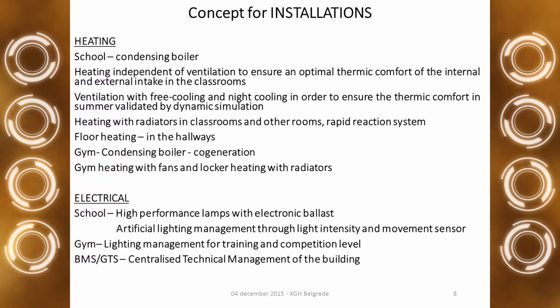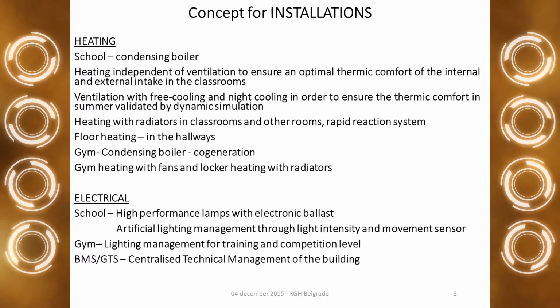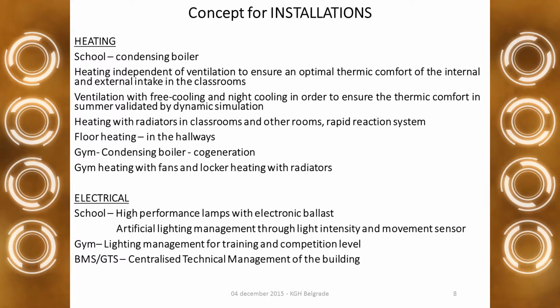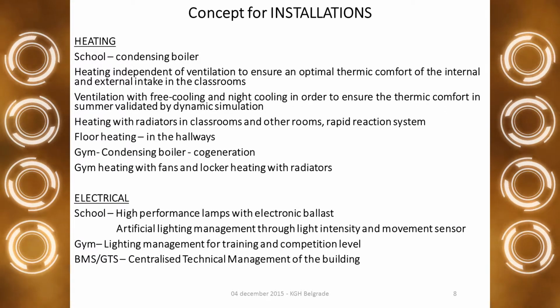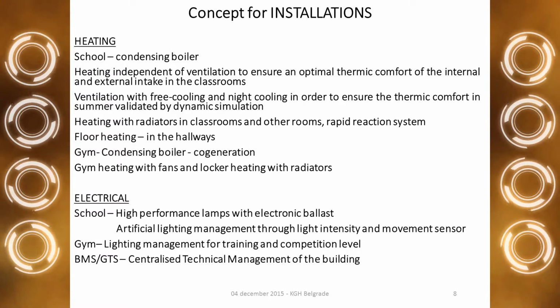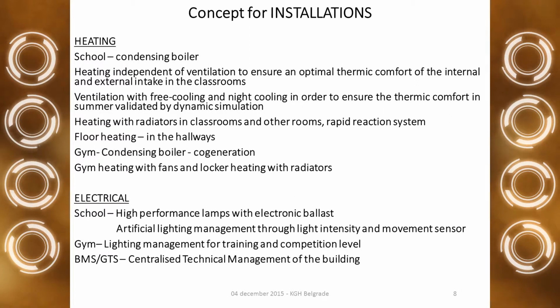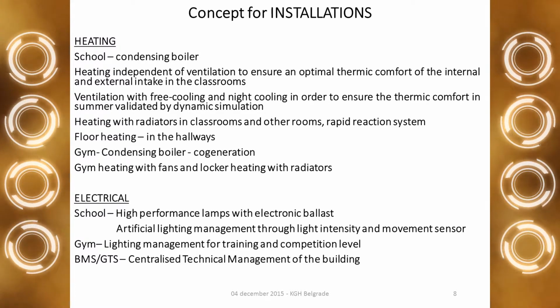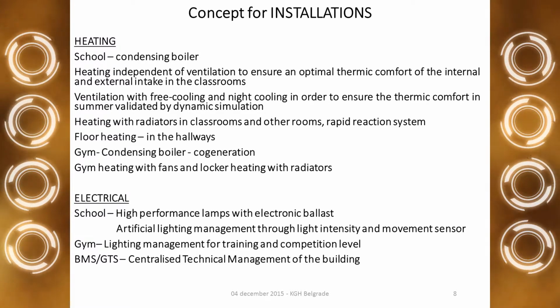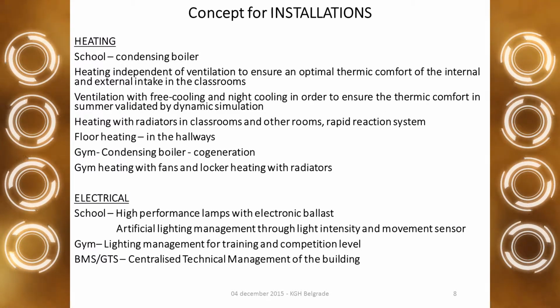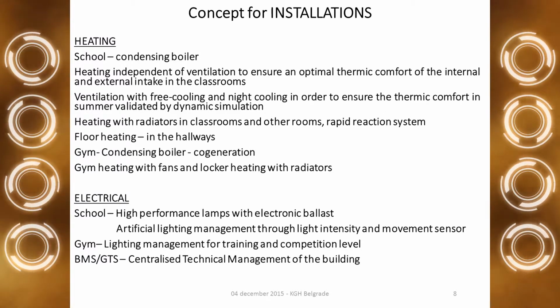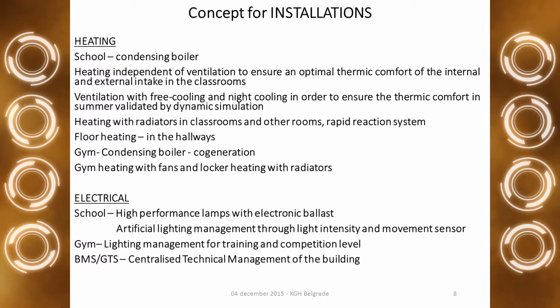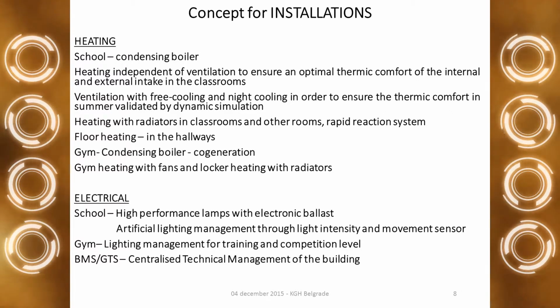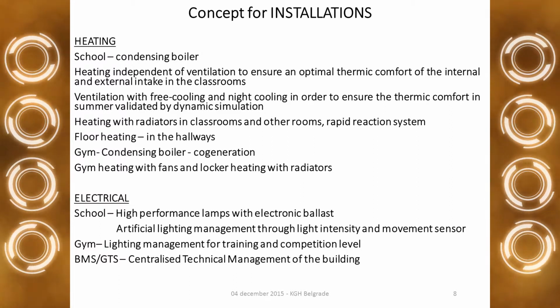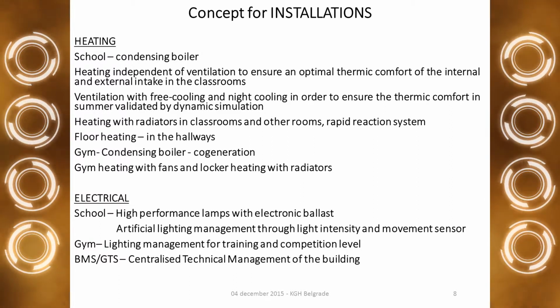Concept for installation. The heating. In the school, the heating plant is with a condensing boiler. The heating is independent of ventilation to ensure optimal thermal comfort, with internal and external intake in the classroom. The ventilation is with free cooling and night cooling in order to ensure thermal comfort in the summer, validated by dynamic simulation. Heating in the classroom is with radiators to have a rapid reaction of the system. In the hall we have floor heating.